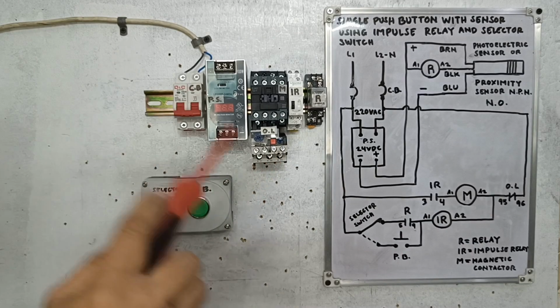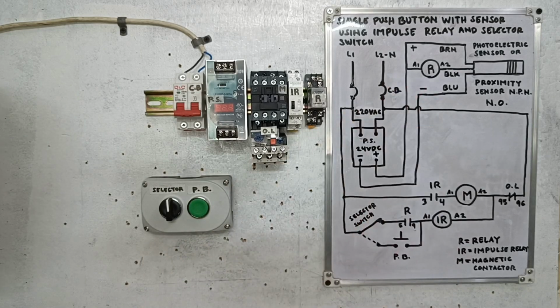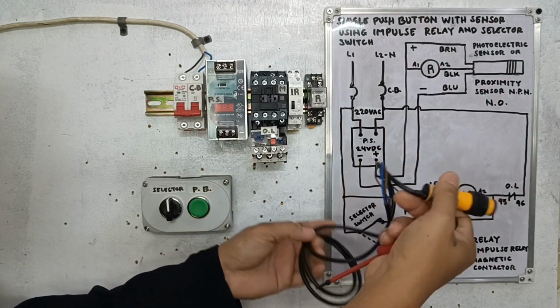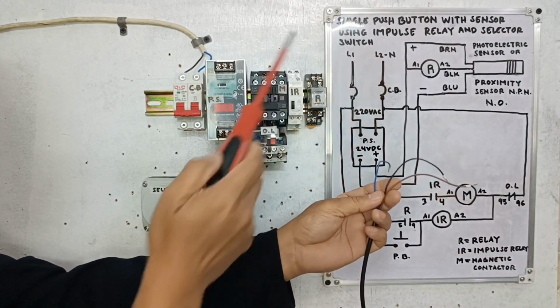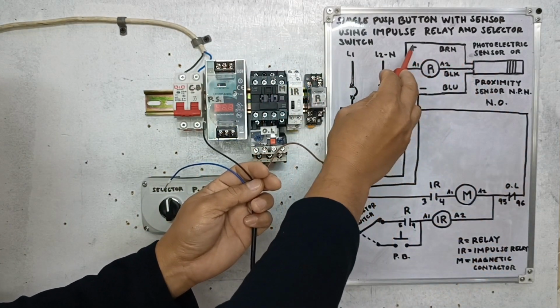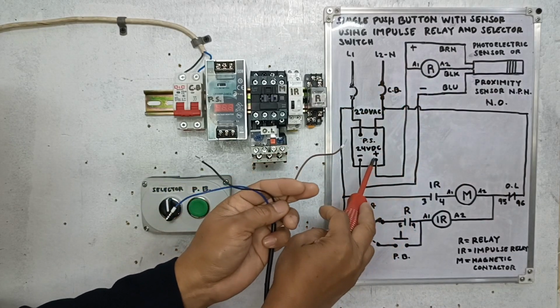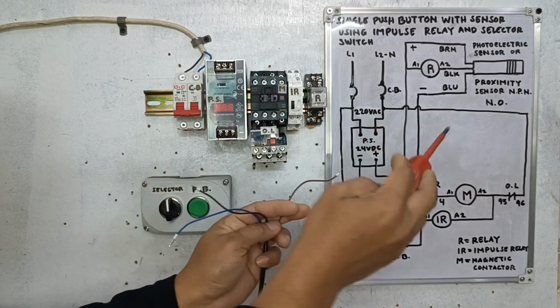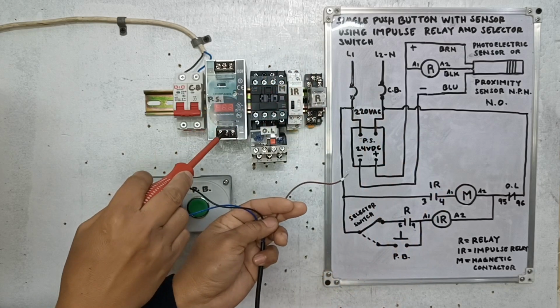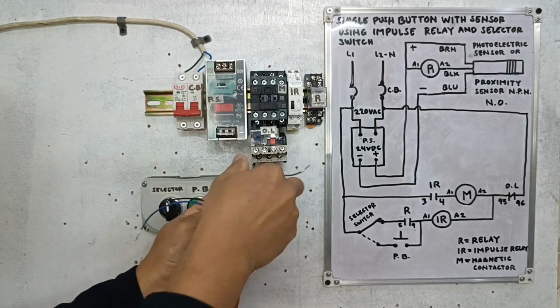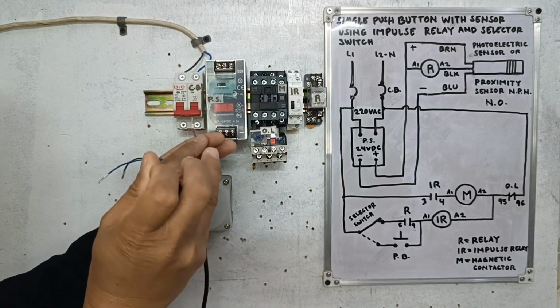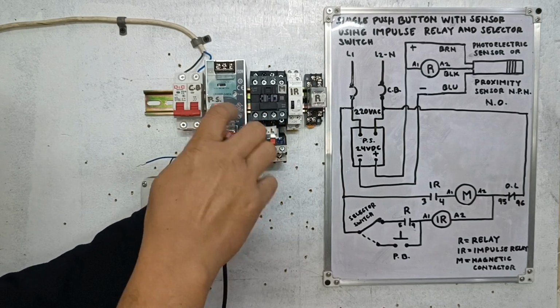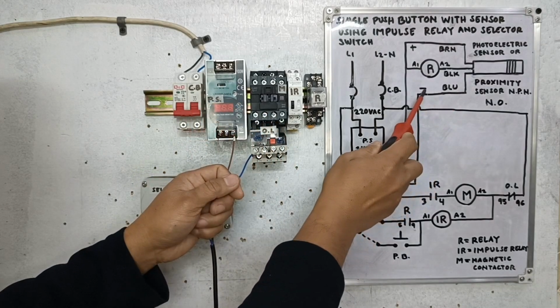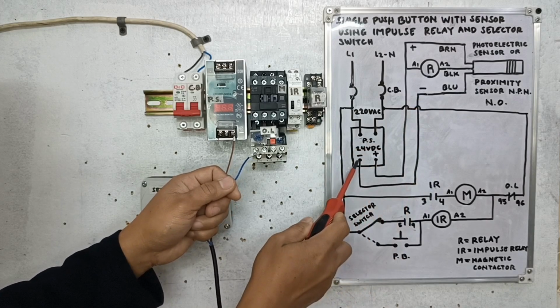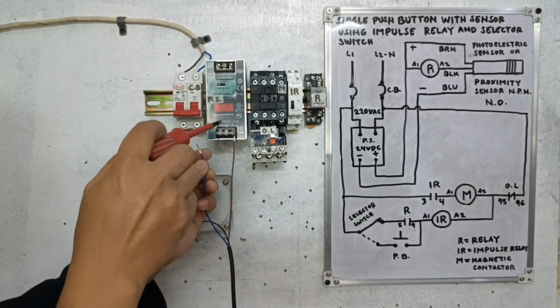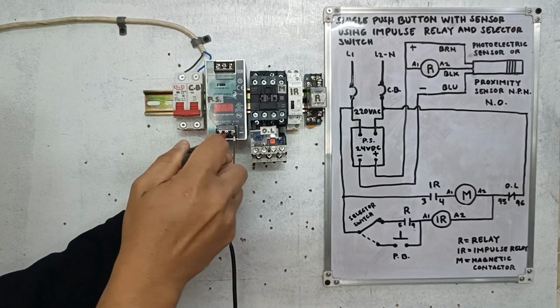Okay guys, let's start now the wiring for this diagram. We wire first the sensor. We are going to follow only the color code of our wire. The brown wire is positive, going to 24 volts DC of the PS, meaning power supply. The positive, guys, is this one. We can connect from here, the positive, and then we tighten. The blue wire is from the negative side. Our negative is here. We can connect here.